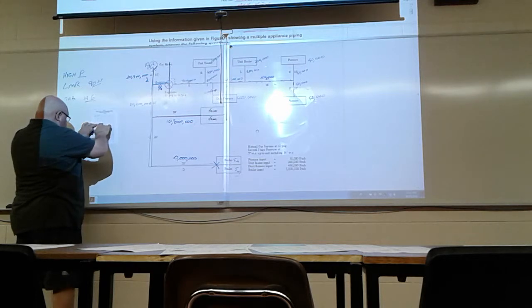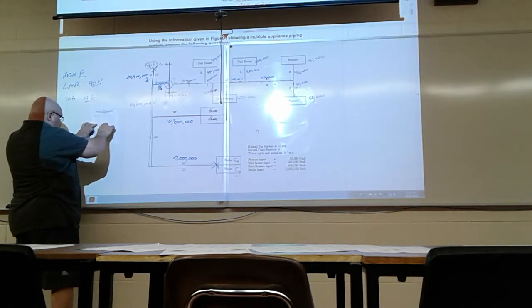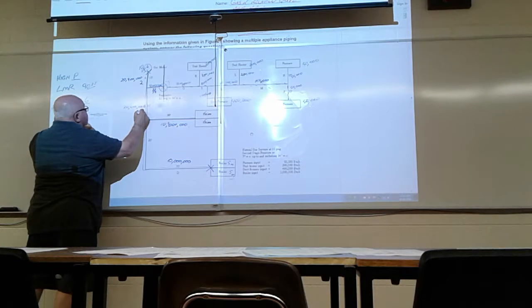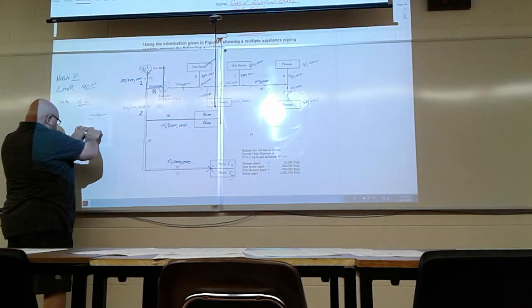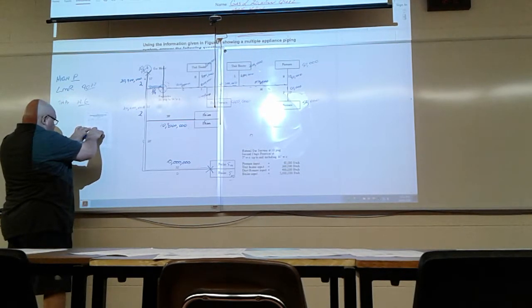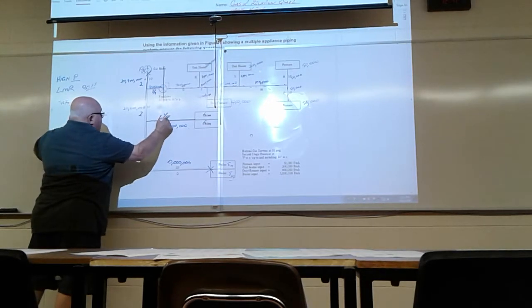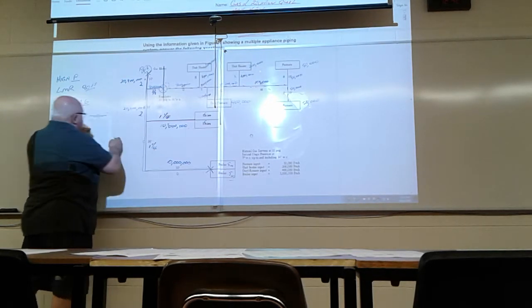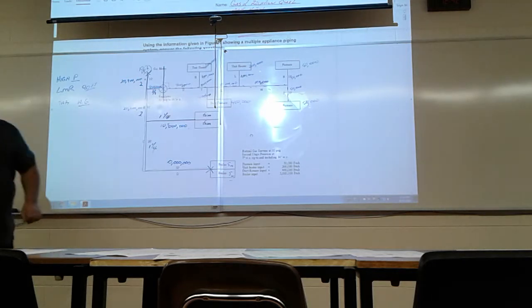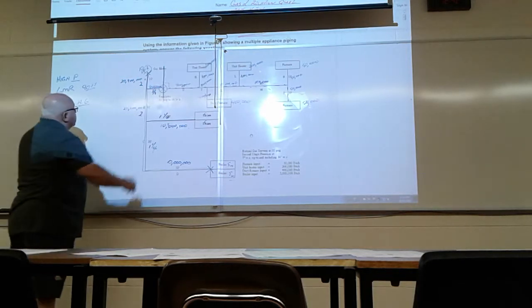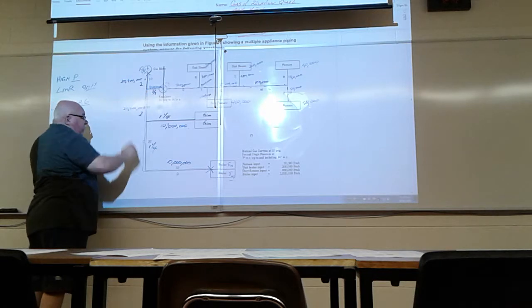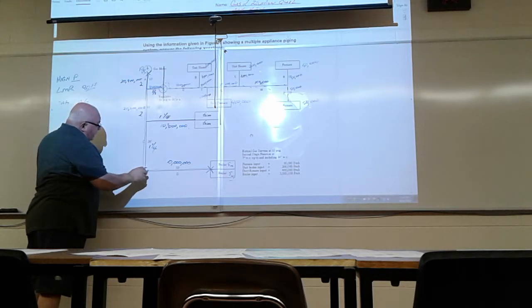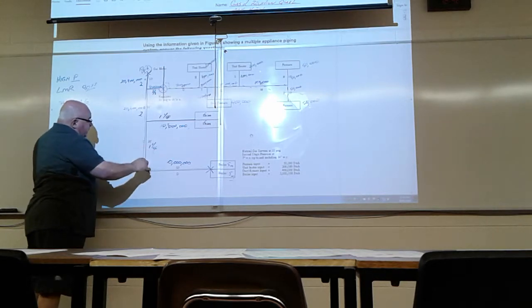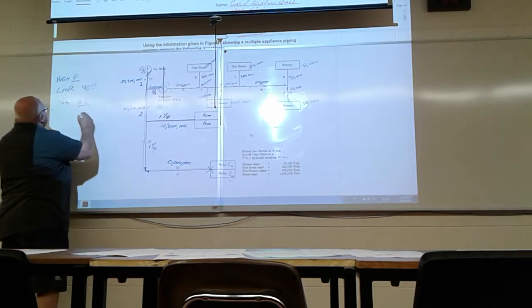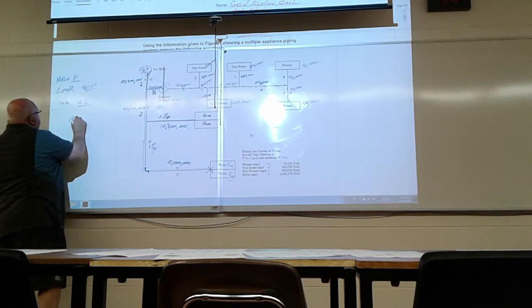20 million BTUs go across 90 feet, equal to or greater than, that's going to be 2 inches. Okay, 10 million BTUs go across and it can drop down to 1.25 inches and 1.25 inches. Okay, so that part of it's done. So that's my starting point. So between the supply of that gas to the furthest appliance, there's only one fitting that changes the direction, which is an elbow. And our initial sizing says that that elbow is 1 1/4 inches. Okay, so that elbow is 1 1/4 inches.